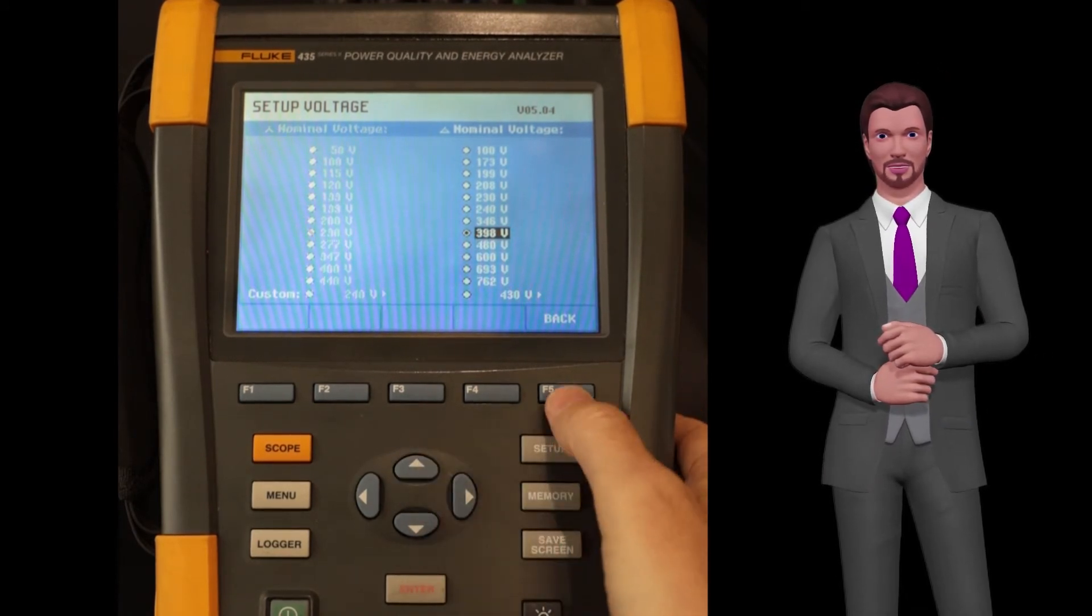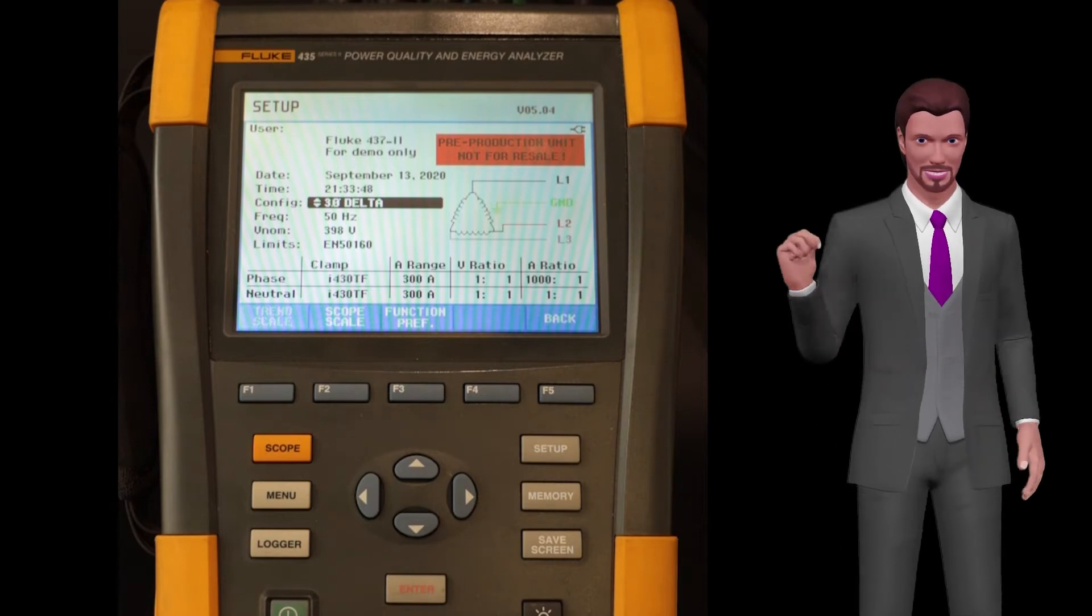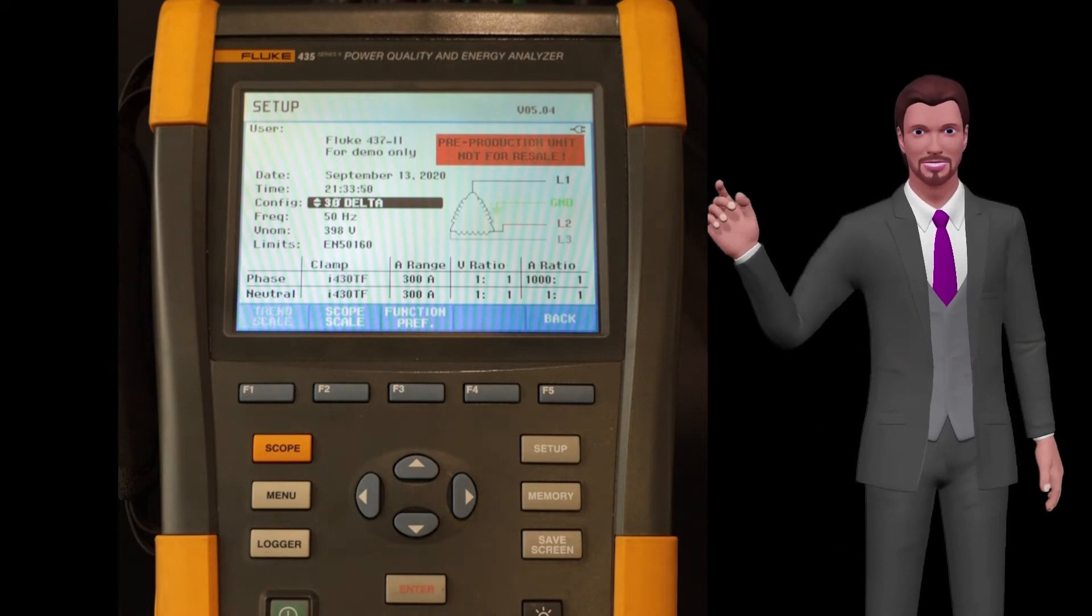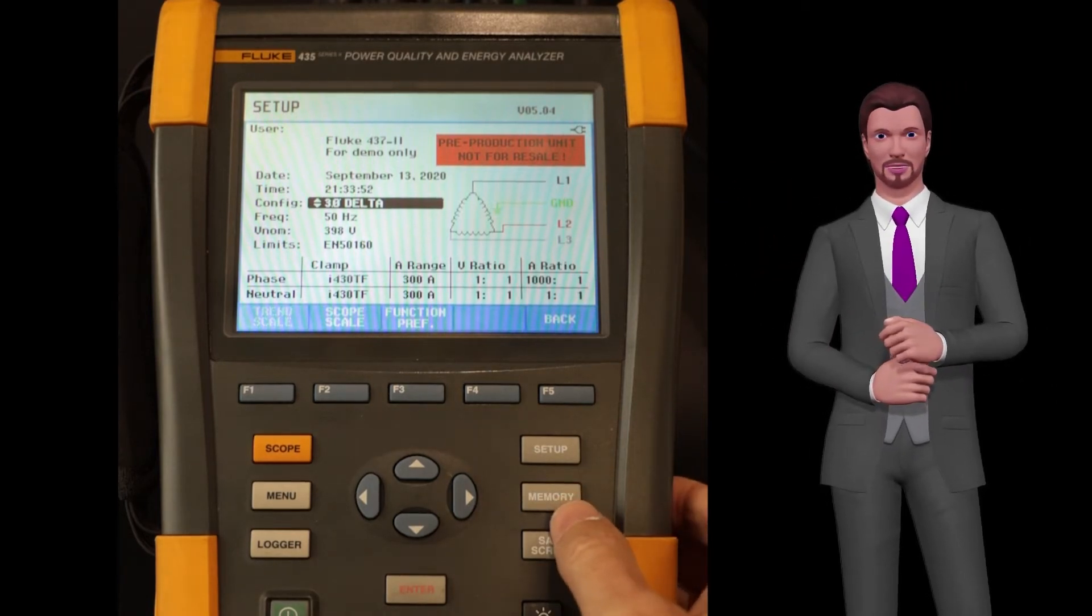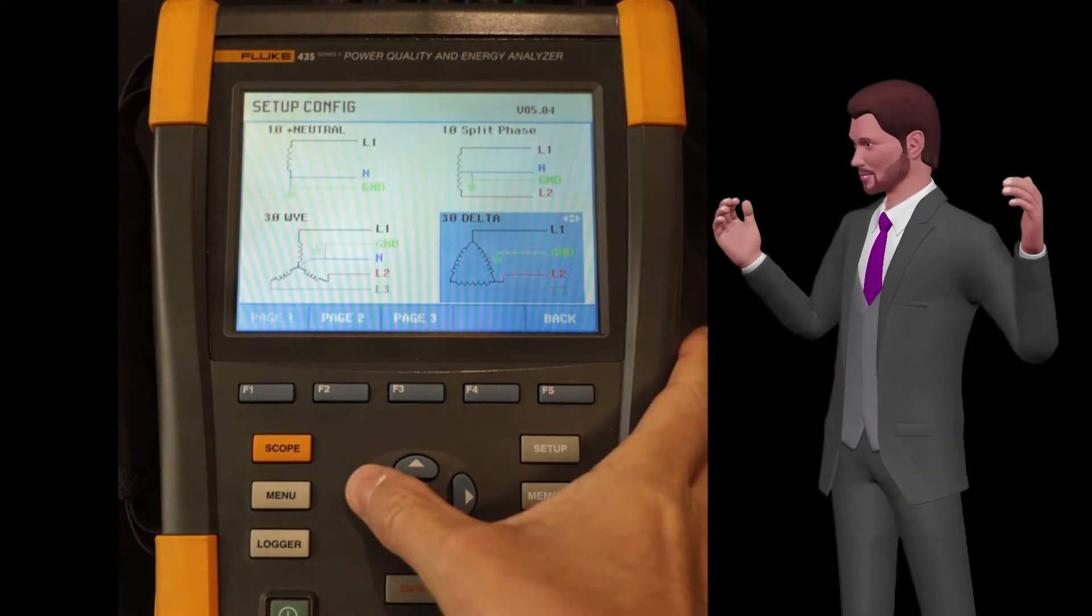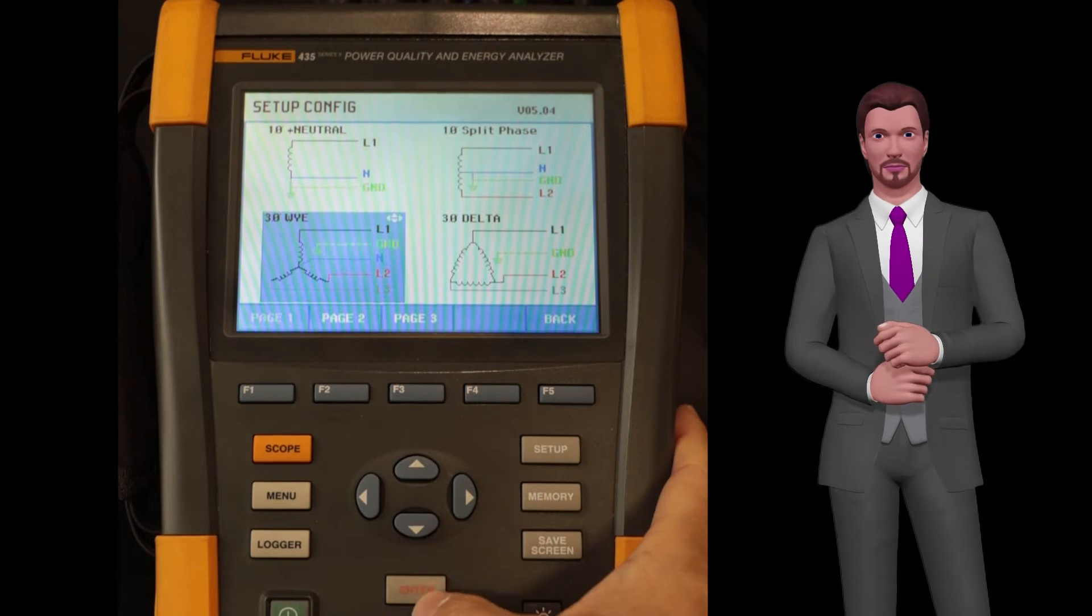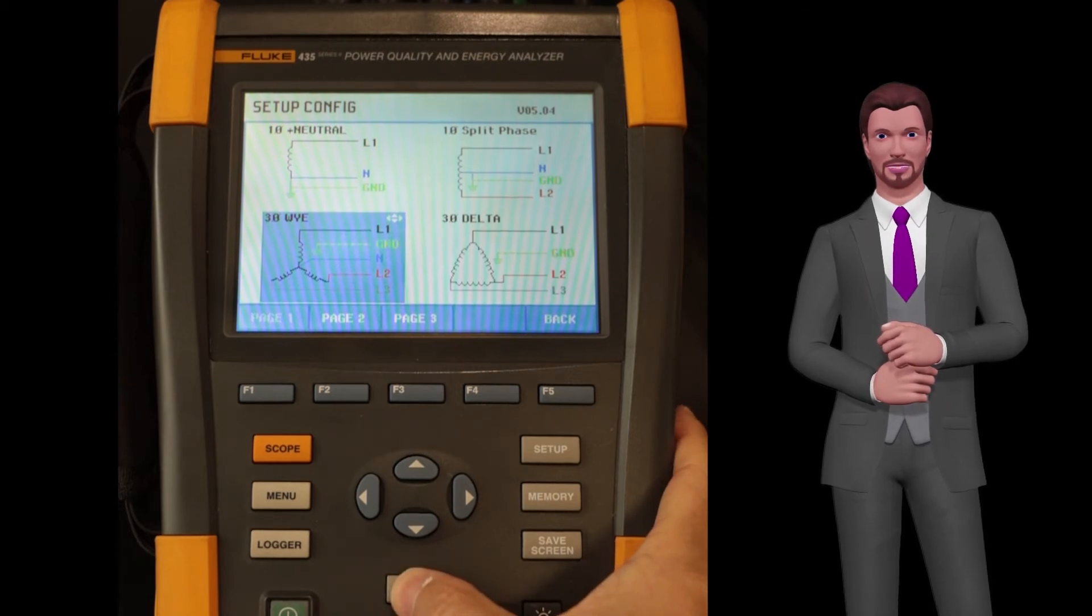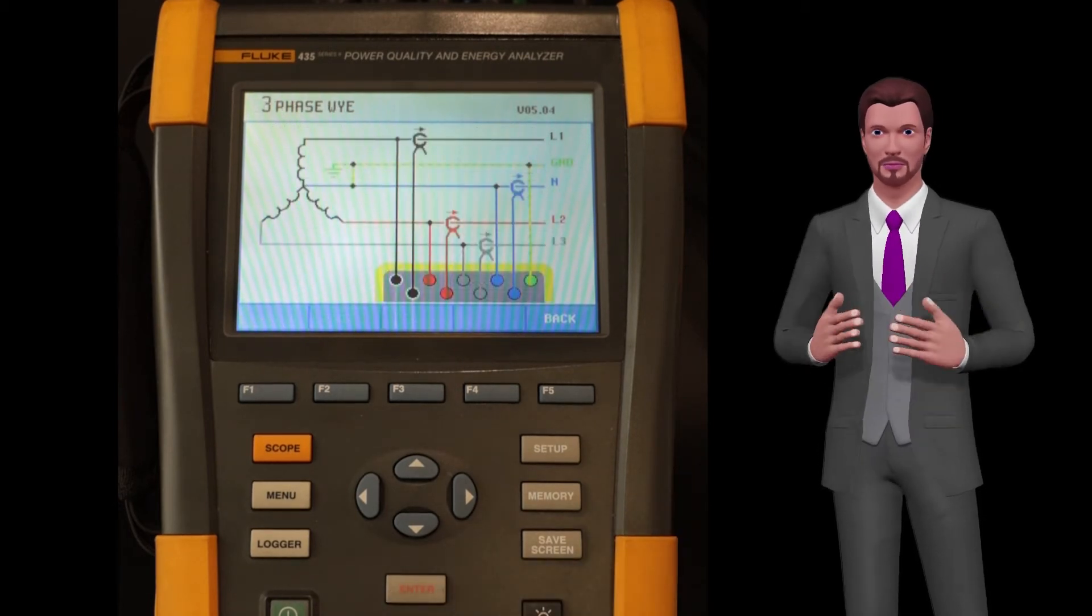But now I want to show you something very important. What nominal voltage value do we have to enter if we choose a star system? Let's try. We press the enter key again and choose with the left arrow the system 3 phase WYE, which is the name given to a star system with a neutral grounded, and then we press the enter key.